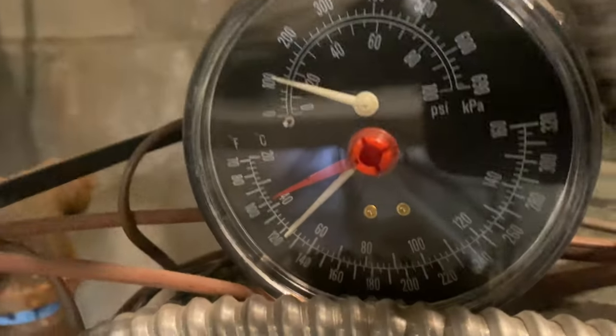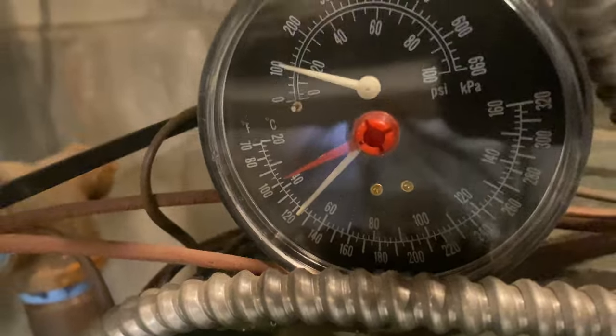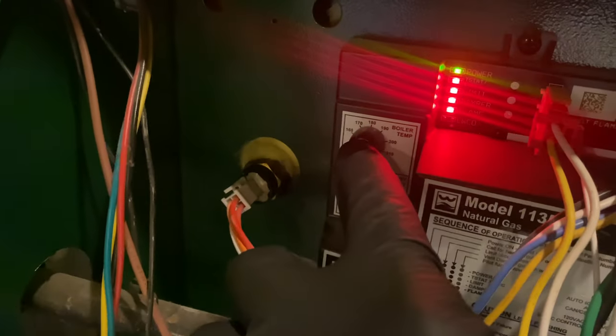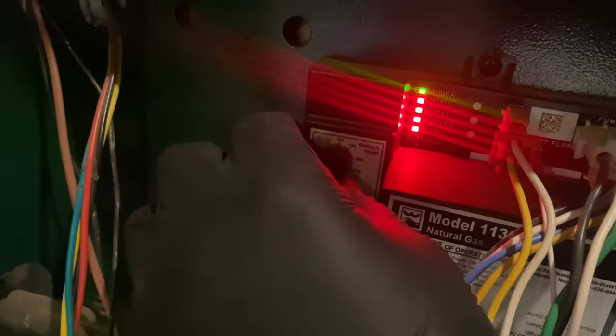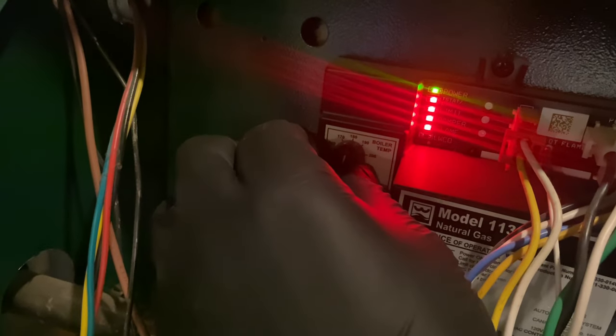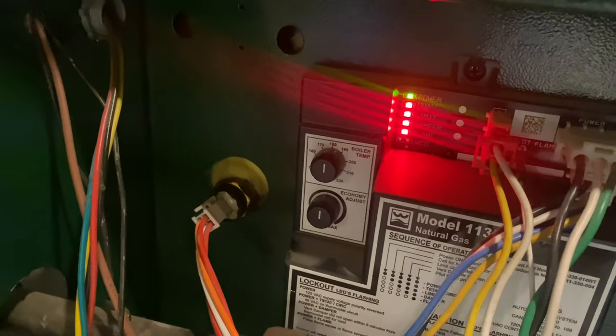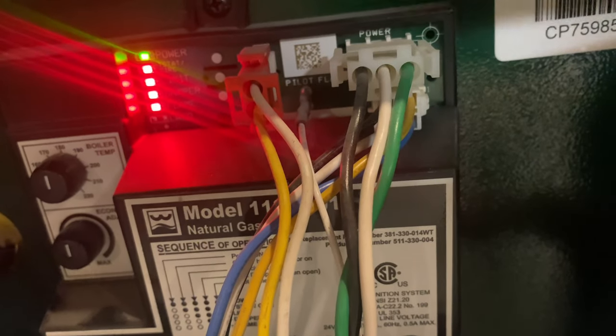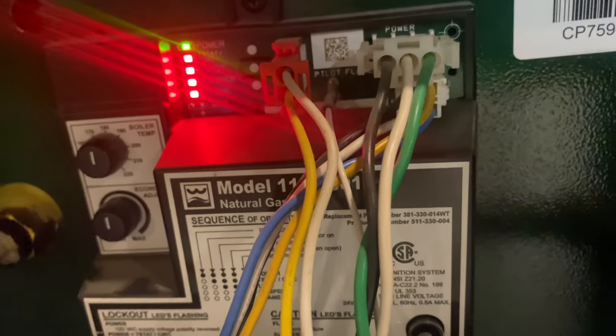Our tridicator gauge is showing 120 degrees, but our boiler control is set for 180, and I just touched it and it went back up again. It turned back on and now all the lights are on. We're going to watch this, because when we first got here, I heard the boiler come on and off in a short fashion, like it was short cycling. So let's see what that's doing.